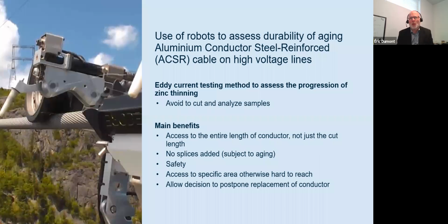This replaces the usual way of doing things, which would be to cut and analyze samples from the line to see if there is some wear within the conductor. There are many benefits to using this robotization technology instead of using only samples. Well, it allows access to the entire length of the conductor, not just a small length. It avoids cutting and adding splices on the line, and splices are sometimes subject to aging, so you want to avoid those as much as possible. By using this probe with a robot, you don't have to add those splices on the line.